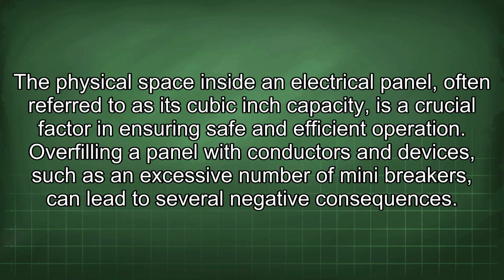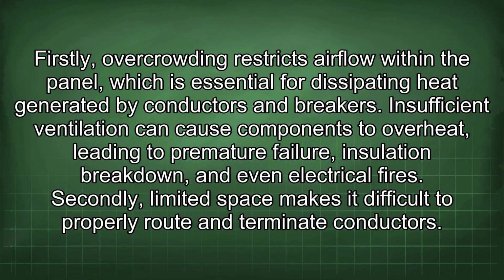The physical space inside an electrical panel, often referred to as its cubic inch capacity, is a crucial factor in ensuring safe and efficient operation. Overfilling a panel with conductors and devices, such as an excessive number of mini breakers, can lead to several negative consequences. Firstly, overcrowding restricts airflow within the panel, which is essential for dissipating heat generated by conductors and breakers. Insufficient ventilation can cause components to overheat, leading to premature failure, insulation breakdown, and even electrical fires.